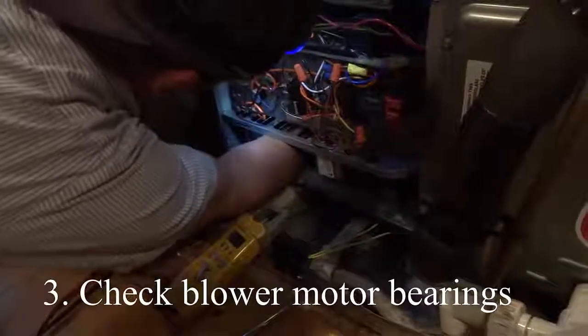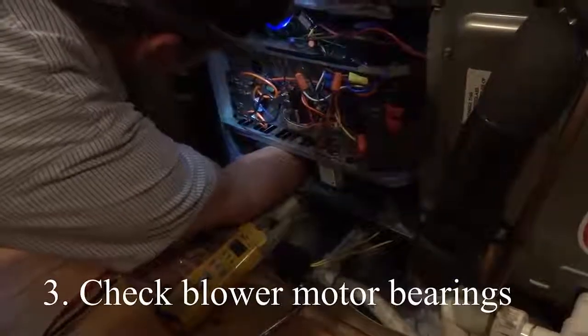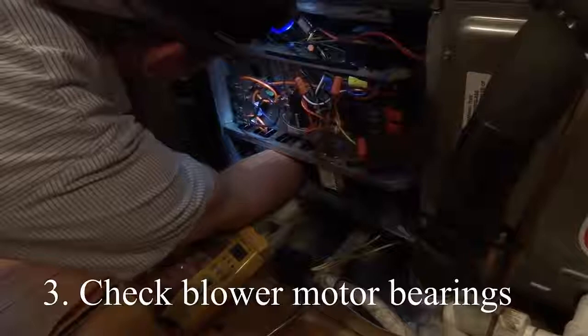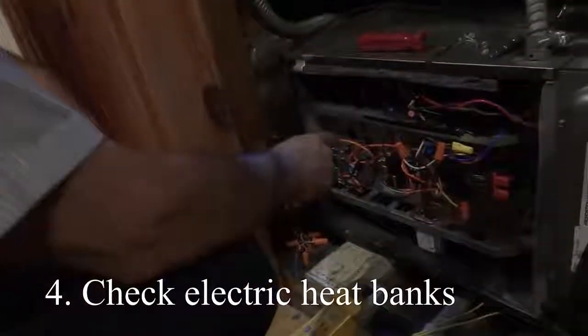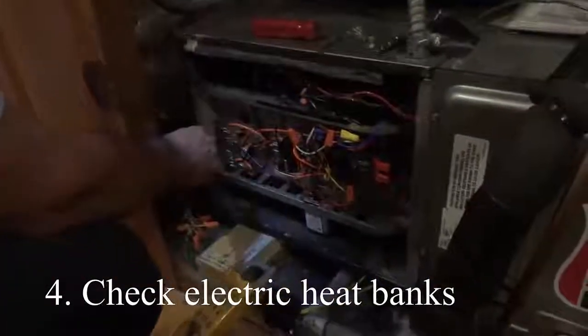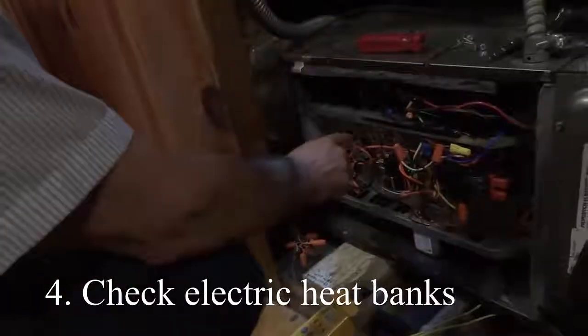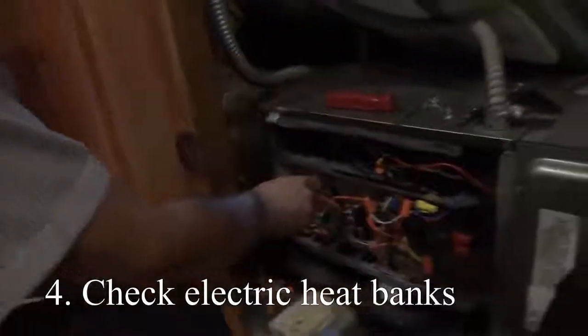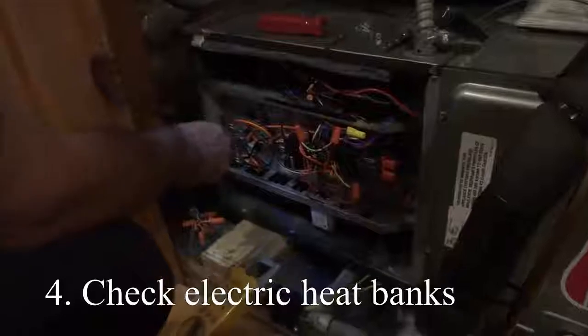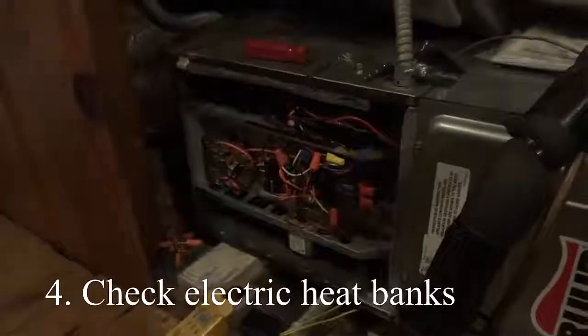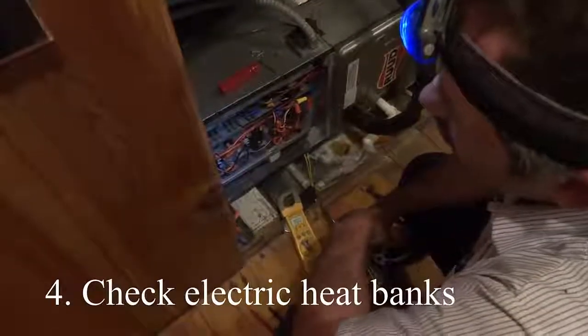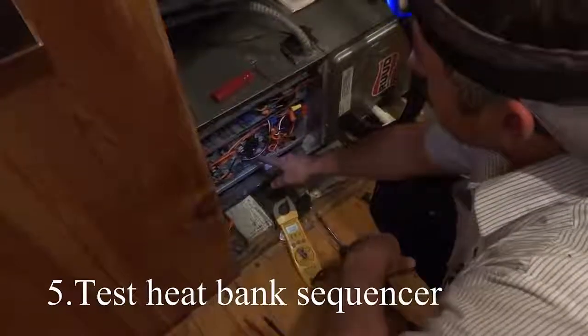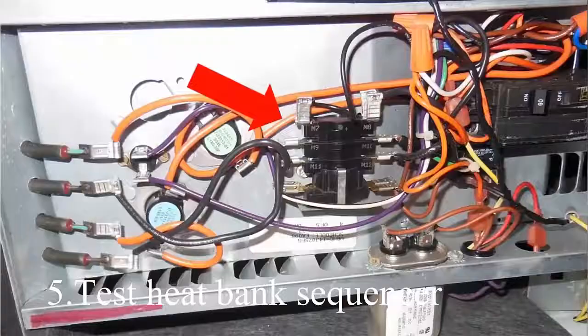Number 3, the blower motor bearings are checked. Bearings by seeing how much play you have in the motor, which is pretty good. Number 4, the heat is turned on and put in emergency heat mode to test the heat banks. Test the heat banks, and by the amperage draw on each heater, I'll know whether they're coming on or not. There is a short time delay between the first and second heat banks coming on to avoid an excessive amperage draw that would dim the house lights.